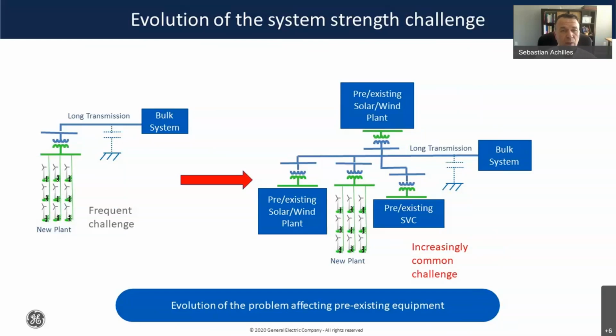So some of the way this challenge is evolving is that sometimes dealing with weak grid is about dealing with the effect on pre-existing power-electronic-driven sources caused by the new devices, in addition to making sure that the new devices can withstand the specific weak grid conditions. And reflecting this in the design criteria for a particular vendor is also more challenging.